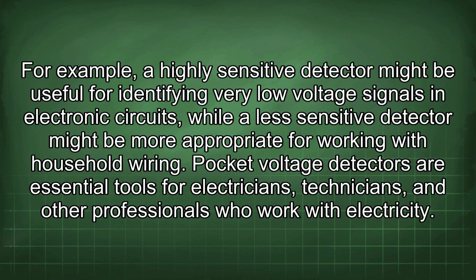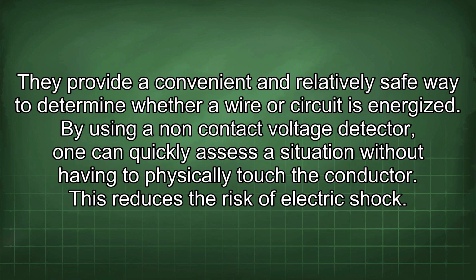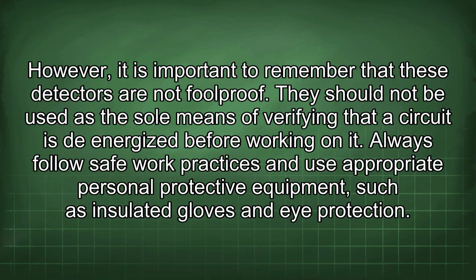Pocket voltage detectors are essential tools for electricians, technicians, and other professionals who work with electricity. They provide a convenient and relatively safe way to determine whether a wire or circuit is energized. By using a non-contact voltage detector, one can quickly assess a situation without having to physically touch the conductor. This reduces the risk of electric shock. However, it is important to remember that these detectors are not foolproof. They should not be used as the sole means of verifying that a circuit is de-energized before working on it. Always follow safe work practices and use appropriate personal protective equipment, such as insulated gloves and eye protection.